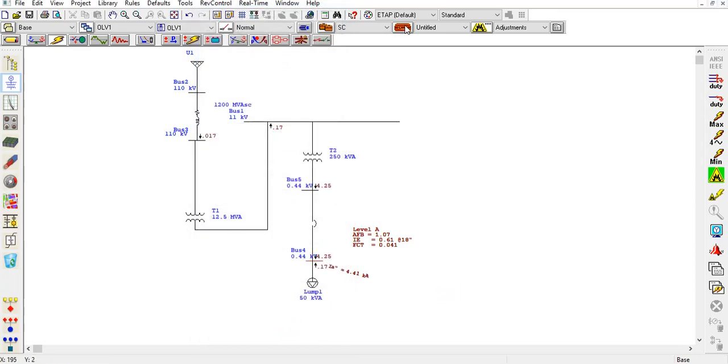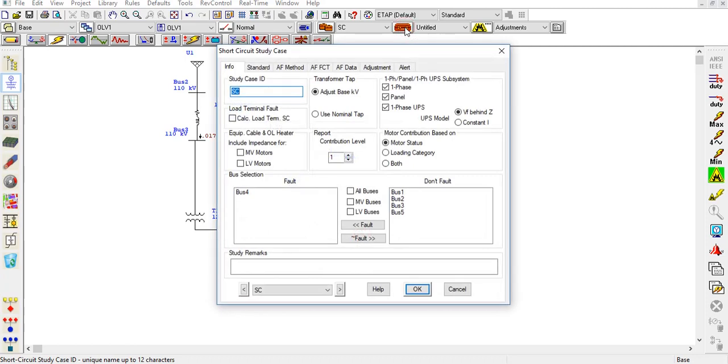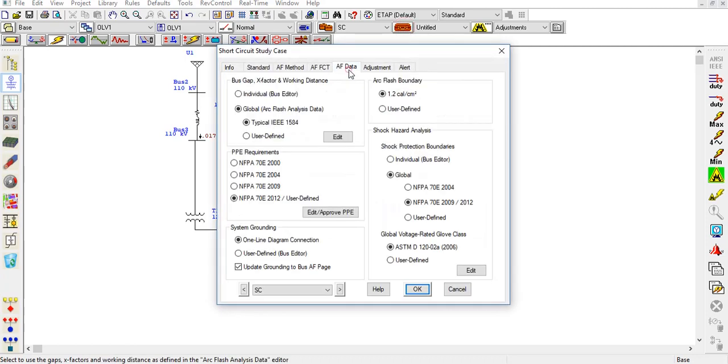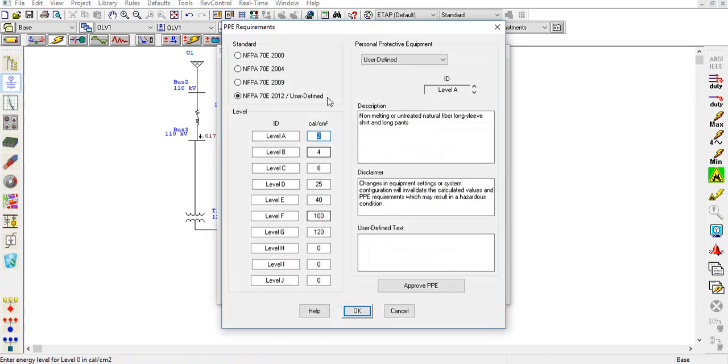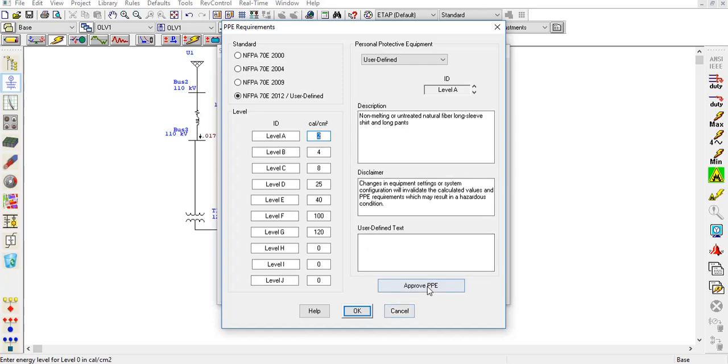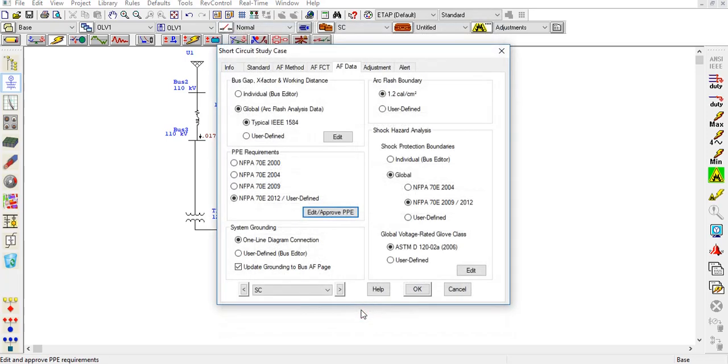Now we will go to the edit study case and arc flash data. You can see that I have chosen NFPA 70E 2012 as the standard. But if you have IEEE sources, you can also choose that. If you want to add your own data, you can come here and define your own levels. Then click approve PPE and it will show you that data.